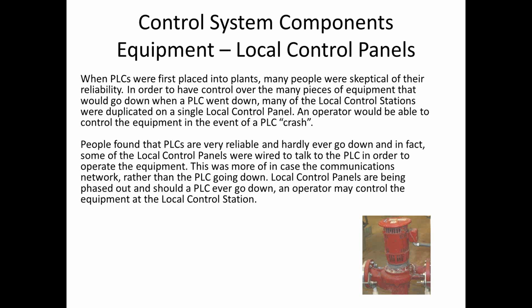When PLCs were first put into the plant, a lot of people were really skeptical about PLCs and were worried that the PLCs would crash and that they wouldn't be able to control the function. And so they anticipated an operator still being able to exercise local control over all of this equipment. And in some instances, that equipment may be spread over a larger geographic area. So what they did is they duplicated the local control station. They put a variety of local control stations in one central location and called that a local control panel. And that allowed an operator to control a variety of equipment from a single location.